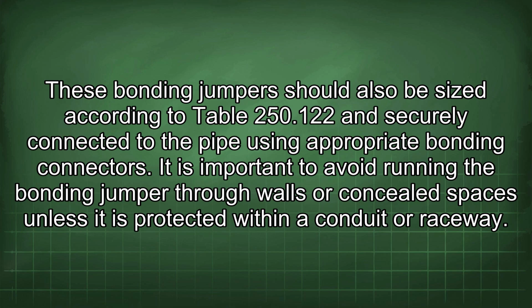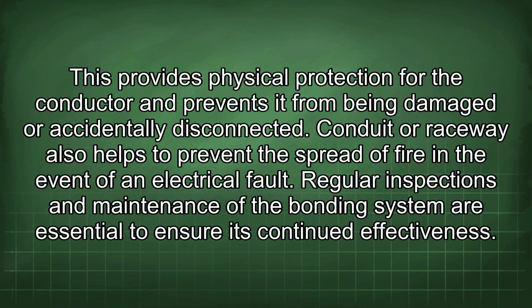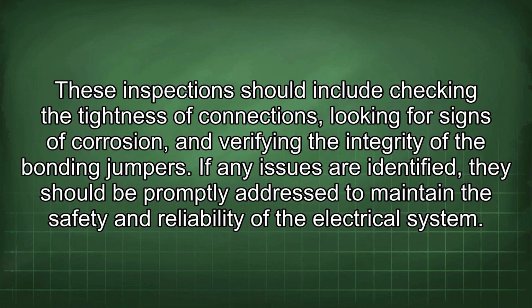It is important to avoid running the bonding jumper through walls or concealed spaces unless it is protected within a conduit or raceway. This provides physical protection for the conductor and prevents it from being damaged or accidentally disconnected. Conduit or raceway also helps to prevent the spread of fire in the event of an electrical fault. Regular inspections and maintenance of the bonding system are essential to ensure its continued effectiveness. These inspections should include checking the tightness of connections, looking for signs of corrosion, and verifying the integrity of the bonding jumpers. If any issues are identified, they should be promptly addressed to maintain the safety and reliability of the electrical system.